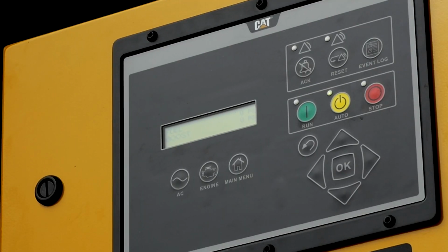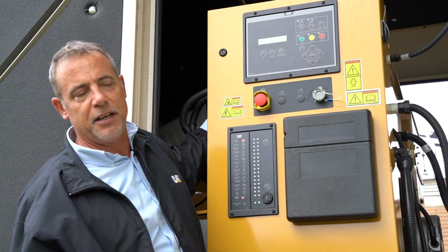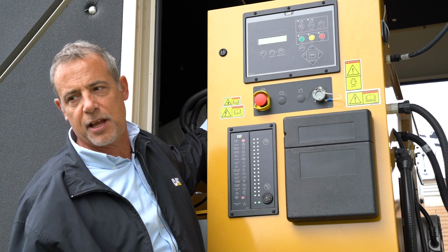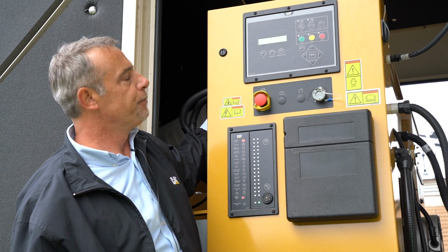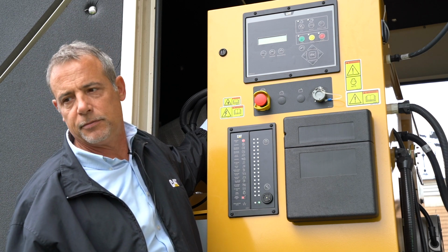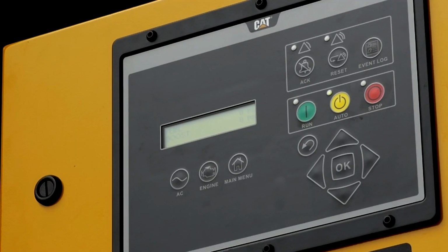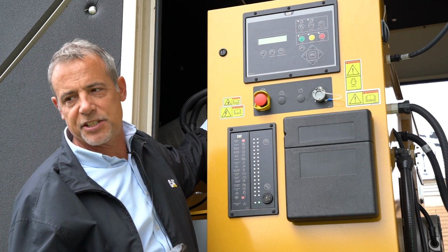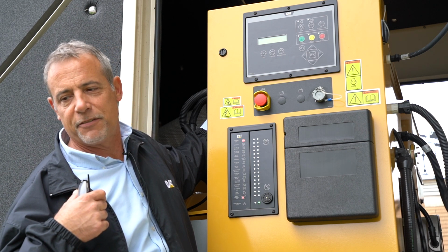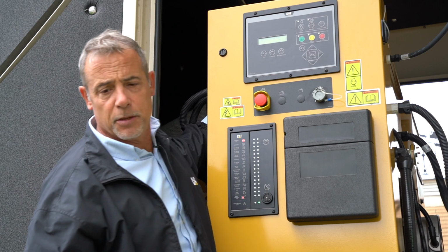The next page tells you your fuel pressure and your boost pressure. The fuel pressure on this runs between 70 and 120 pounds on the low pressure side. If you're down around 50, 60 pounds, you probably got a clogged fuel filter. You might want to think about changing it. The boost pressure is just the amount of pressure the turbo's building up. With the load that I see in the building, you're never even going to spin that turbo. It's never going to get even spooled up. But if you had a power issue, this is where we would look to see what kind of pressure is in the system.